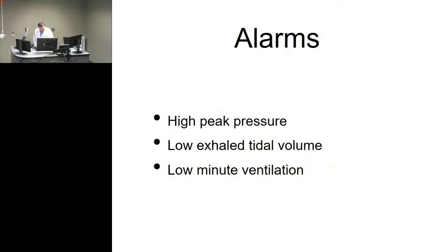So when it comes to alarms, the probably 3 biggest alarms you're going to see are going to be your high peak pressure, your low exhaled tidal volume, or a low minute ventilation. And this will come back to things we already touched on a little bit earlier.